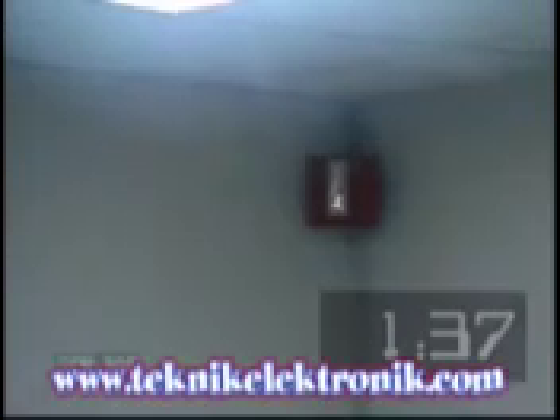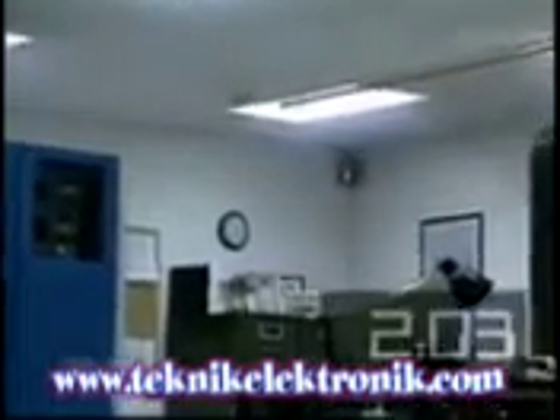Suppose instead you had an FM200 waterless system as your primary fire protection system in this room. Suppose again it is after hours and an electrical malfunction inside an equipment cabinet causes a spark to ignite. 32 seconds. The system's detector senses the first whiff of combustion. 1 minute and 3 seconds. A first alarm is sounded. 1 minute and 35 seconds. The system sounds a second alarm and begins a 30-second pre-discharge countdown. 2 minutes, 5 seconds. FM200 is released. 10 seconds later, the fire is out.